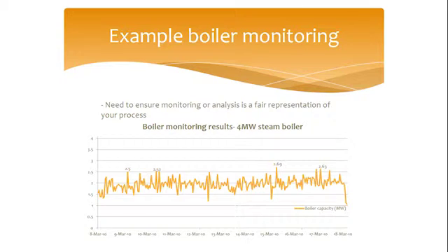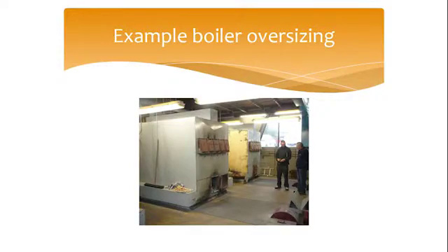One thing you need to think about if you're going down this road of heat metering is making sure you do it during your peak period. You don't want to be measuring a summer heat load when your peak demand's in winter. Sounds pretty obvious, but you want to make sure you're doing that. For anyone here today that might be looking to switch and asking what our boiler is doing, this is the perfect time to be doing that monitoring and collecting that information for your system.